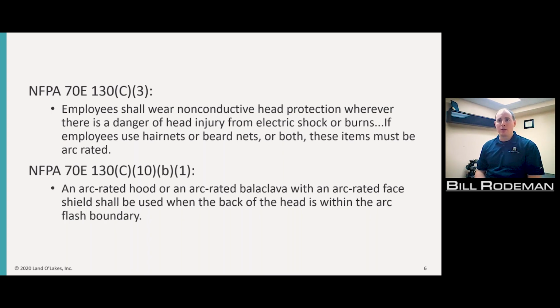Later in Article 130 C10B1, it states an arc rated hood or an arc rated balaclava with an arc rated face shield shall be used whenever the back of the head is within the arc flash boundary. So if I'm working on equipment where the arc flash could be large enough to engulf the back of my head, I need to make sure it's protected.